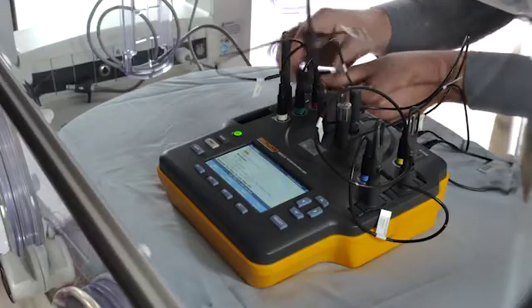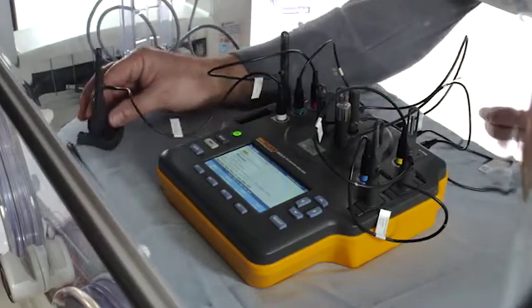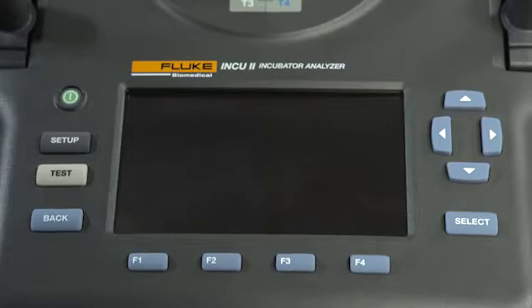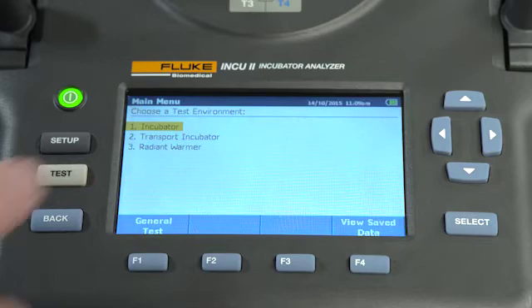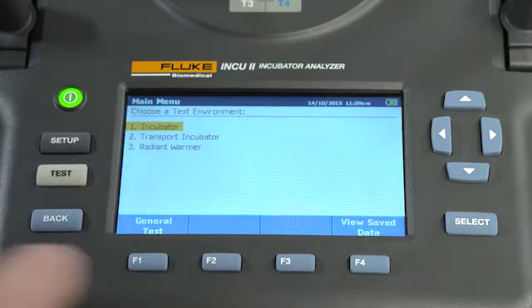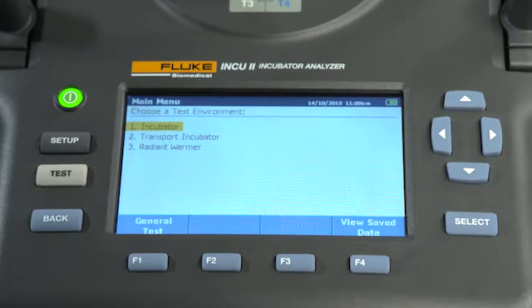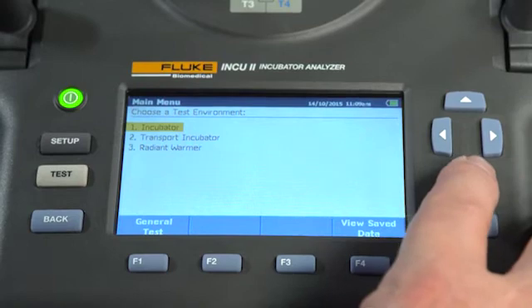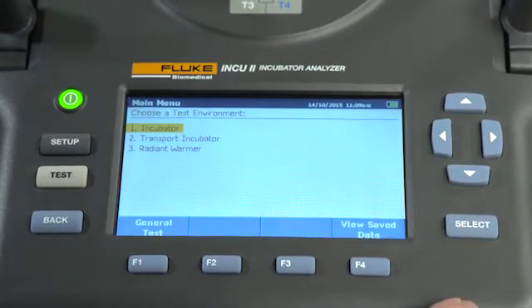Remove and set up the temperature tripods and sensors. Position them in the middle of each quadrant of the mattress. When you first turn on the INCU II, it will do a self-check. When it's ready to test, the main menu will appear. Select a test environment and choose a general test or view saved tests. If you're going to run an incubator test, highlight incubator from the test environment option using the navigational arrow keys and then press select.